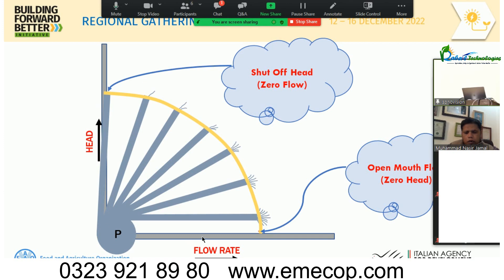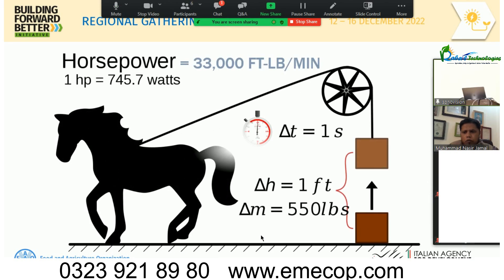On the right extreme of the pump curve we have maximum flow rate but zero head or pressure. On the left extreme we have maximum head but zero flow — this is called shut-off head. The right extreme is called open mouth flow or zero head. Horsepower is the unit of power, roughly equal to 746 watts or 33,000 foot-pounds per minute of work done.